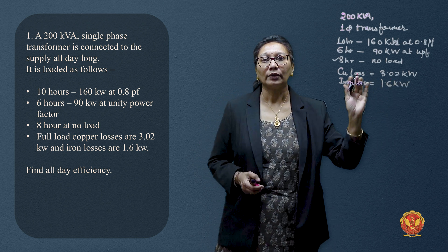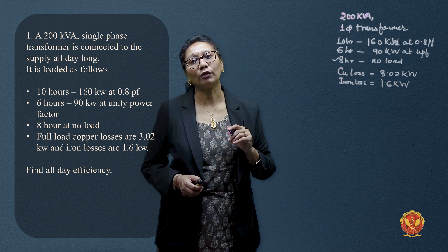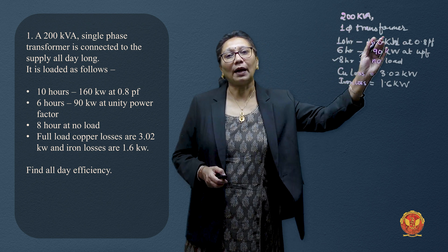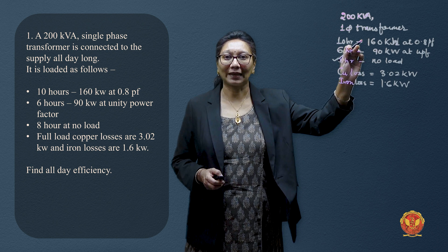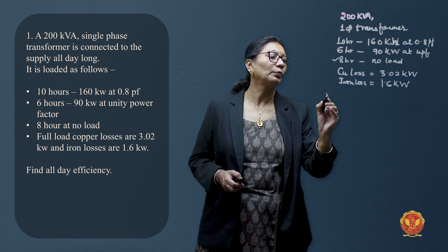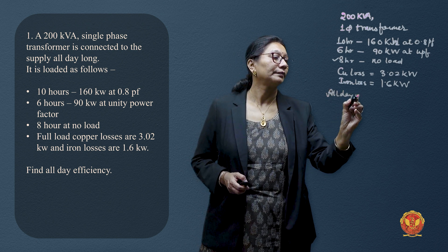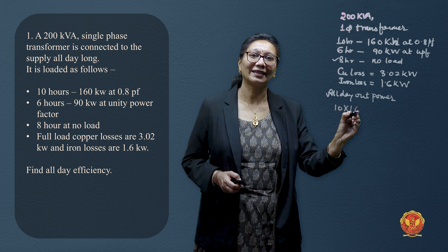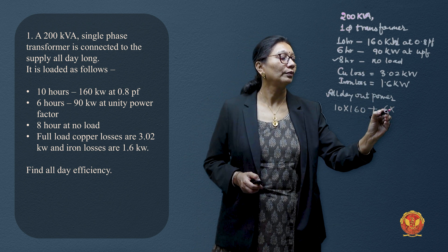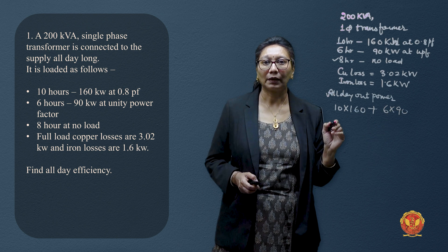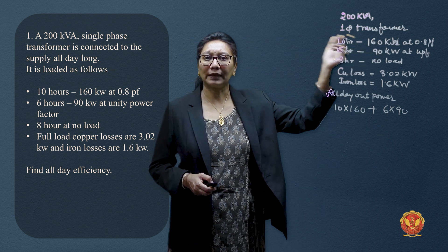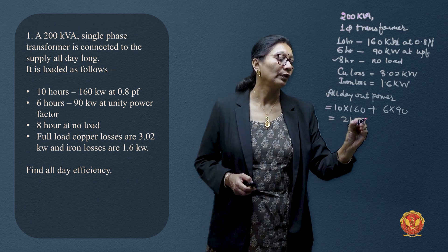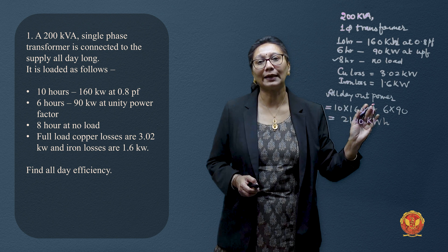We have to calculate all-day efficiency. All-day output power is calculated by multiplying power by hours of working. So: all-day output = (10 hours × 160 kW) + (6 hours × 90 kW at unity power factor). Since ratings are already in kW, this comes out to 2140 kWh of energy consumed by the load.